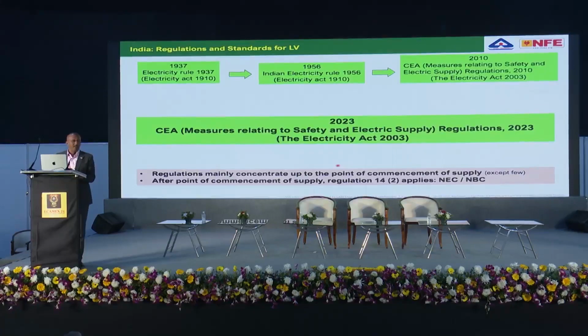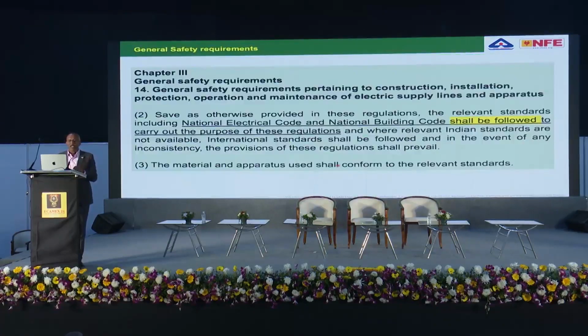After the point of commencement of supply, regulation 14, sub-regulation number 2 applies, where you can see: save otherwise provided in these regulations, the relevant standard including National Electrical Code of India shall be followed. For the first time in our country, the regulation is using the word shall. Shall be followed means mandatory. It must be followed. Until now, in the 2010 regulation, the wording was may be followed.